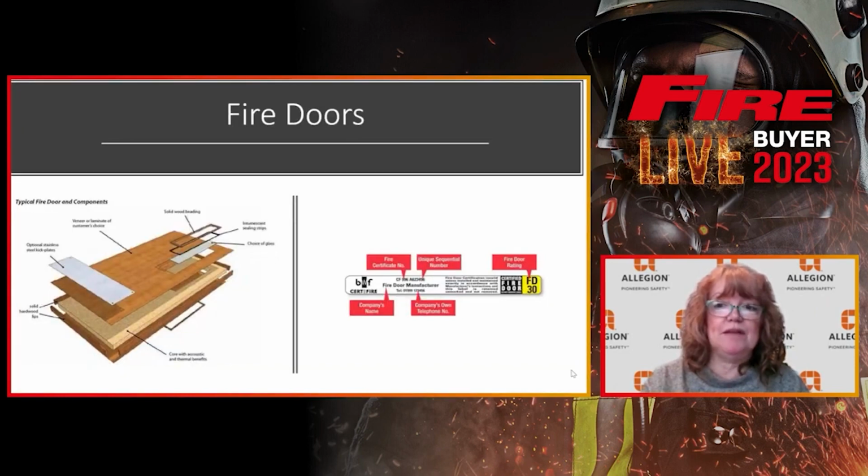As you can see from the slide, a fire door itself is made up of components. A flush or moulded panel door is made of an outer framing material, door core and an outer skin. The outer skin provides the decorative appeal of the door, whereas its fire resistance depends on the ability of the framing and core materials to withstand fire for the required length of time.